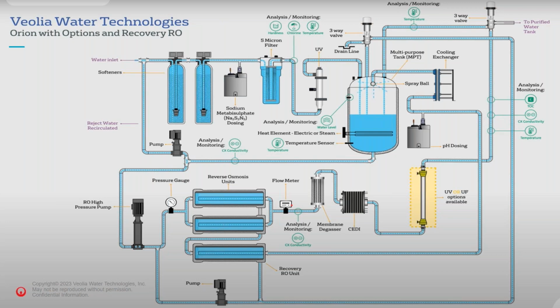So if this was a 16-hour shift and an 8-hour shut-off, shall we say, or no demand, during the 16 hours you have the recovery RO to reduce the amount of water you're throwing down the drain during service by 50%. It's a 50% recovery RO here. So you're halving the amount of water you're throwing down the drain for 16 hours a day, 365 days a year, so it all adds up. And then on recycle, we recover all the water because we've included a cooling exchanger on the line here. That mitigates any temperature increase within the recirculation phase, which may be running for about 8 hours a day. So again, 8 hours a day, 365 days a year, you're throwing less water down the drain on the recycle phase and also during service with the recovery RO. So those are our two main energy saving devices or water footprint reducing devices.